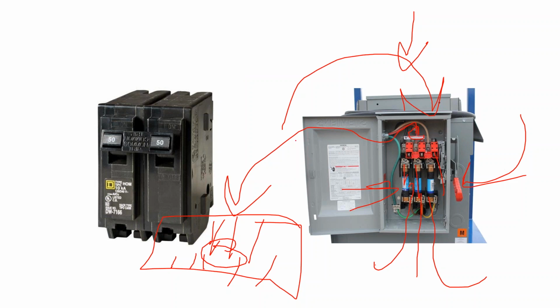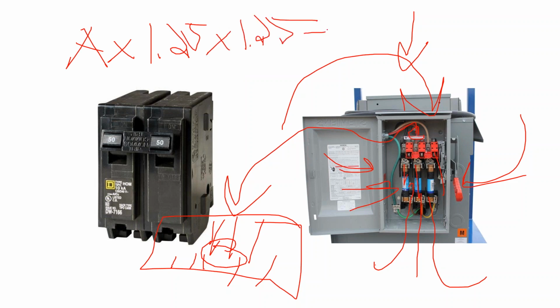You know, what I saw is the way you do these fuse sizes is you take your amperage and multiply by 1.25, and in solar you have this other additional 1.25, and that gives you your new amperage, and then you round up to the nearest fuse size. Well, I've seen an instance where the solar installer's calculation was right on the border, and I don't know what happened. Maybe they went to Home Depot or their electric supply store, and there were only 5 amp fuses or 10 amp fuses available instead of 15 amp.